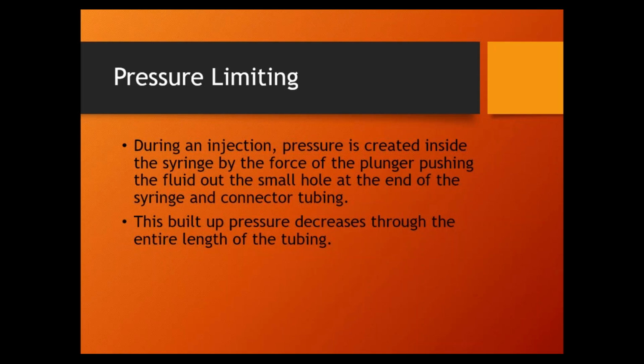So, worst case scenario, if something has happened and we have a clogged catheter, there is debris, it happens. There's debris in the syringe or in the connective tubing and it hits that catheter tubing and it gets clogged. Now we do have 1,000 PSI from the syringe all the way up to wherever that occlusion is. So it is possible to get that high pressure to the catheter. That's why they put ratings on the catheters and the IV needles. They don't exceed this pressure because, worst case scenario, if we get the pressure here, it can't handle anything else.